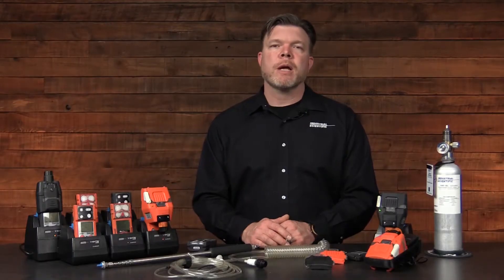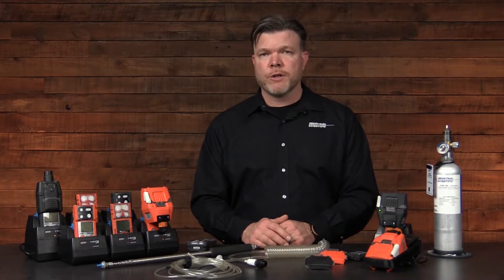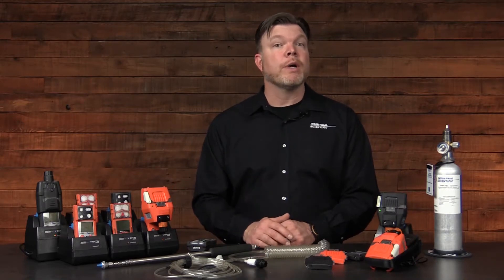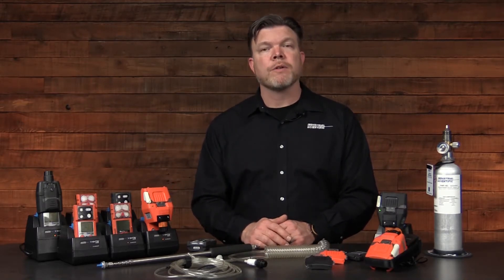The Ventis slide-on pump also includes LEDs and audible alarms to alert the user of the condition of the pump. For example, a solid green light indicates the battery is fully charged. If the green light is blinking, it indicates the battery is charging. If it's a yellow blinking light, then there's a fault or an error with the charging. There are also red LEDs and an audible alarm that will alert the user when there's a pump fault.